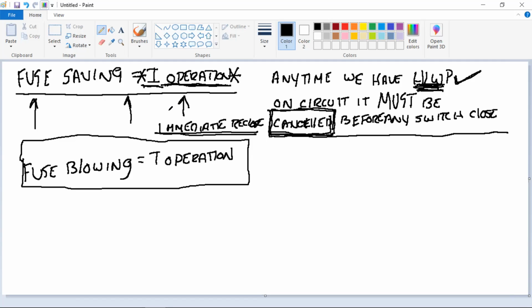In normal day-to-day service, when that breaker was in automatic, the first operation was time. When we called in, even with the fuse, and that is a fuse blowing scheme, the breaker went to what? First operation, what? Instantaneous. Right. We had that changed. So every time, even on this fuse blowing scheme, when we got a hotline work permit, it gave us an I operation. So even on a fuse blowing scheme, the breaker is going to give you an I operation. So do you have to cancel your hotline work permit for both a fuse saving and fuse blowing scheme? Yes. Yes. Thank you very much.